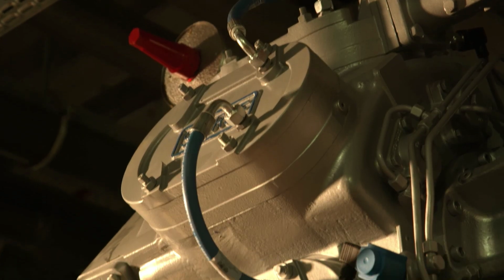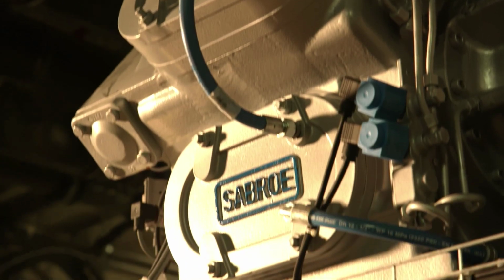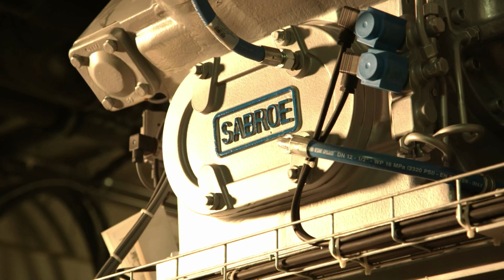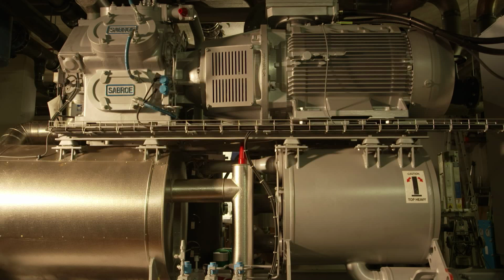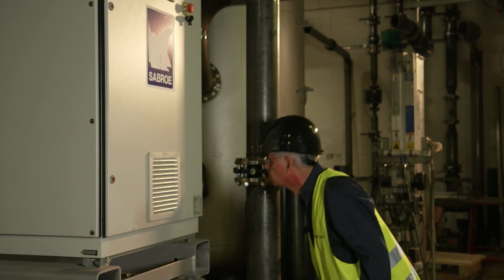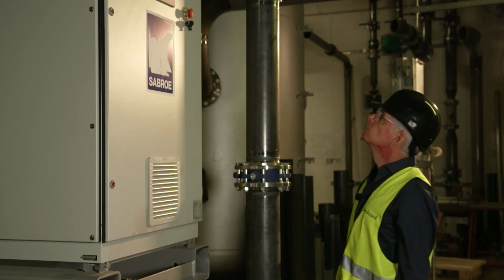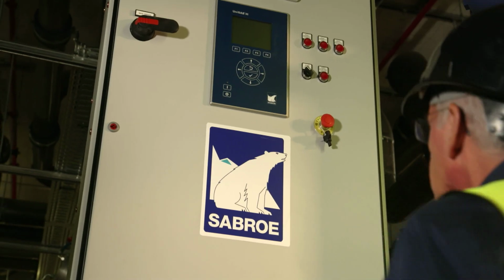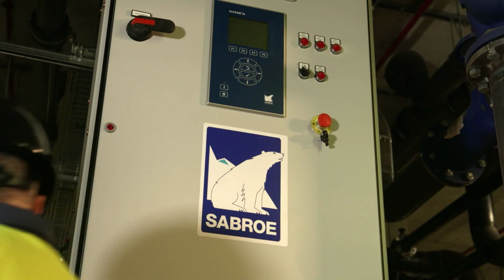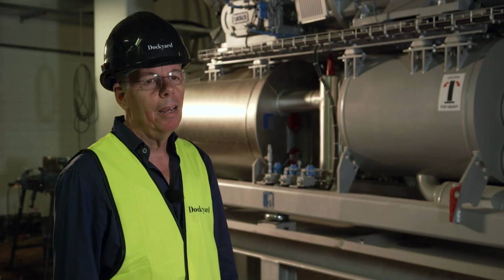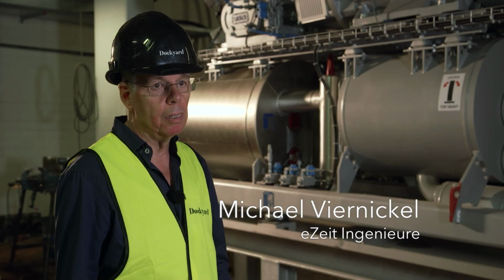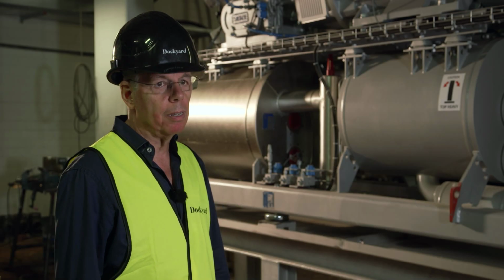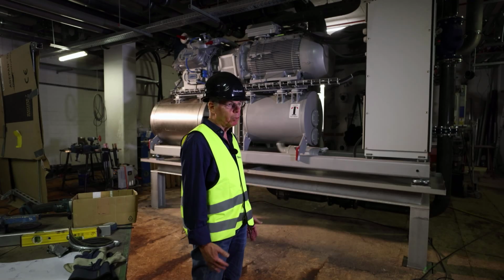The storage tank in the former railroad tunnel makes it possible to store the heat from the summer and use it optimally in the winter. 3 large heat pumps in the basement of the building are vital for the energy management. Together, they have an output of over 1 megawatt. Conventional heat pumps use refrigerants that have a high global warming potential if they are handled improperly and leak. That's why we use heat pumps here that use ammonia, a natural refrigerant.